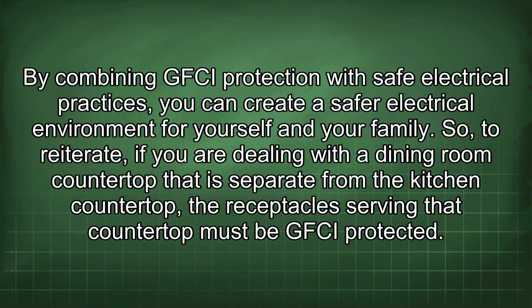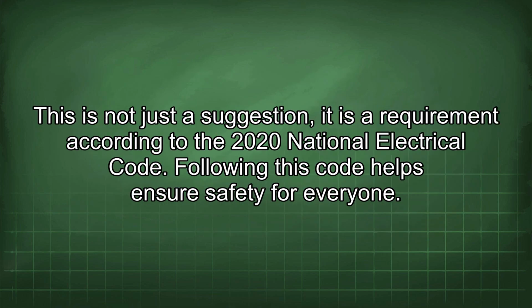So, to reiterate, if you are dealing with a dining room countertop that is separate from the kitchen countertop, the receptacles serving that countertop must be GFCI protected. This is not just a suggestion, it is a requirement according to the 2020 National Electrical Code. Following this code helps ensure safety for everyone.